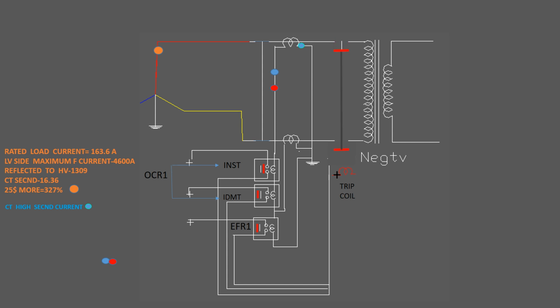So what we have seen: when the 25% more LV current is reflected to the HV side, that is 1309 ampere, but in the CT secondary it is 16.36 or 327%. When this current reaches the CT secondary and passes through the instantaneous relay, it will energize and make its normally open contact close, and the positive will extend up to the trip coil, and the trip coil will open the circuit breaker. So this is the basic idea in the electromagnetic relay, and this is programmed in the numerical relay.